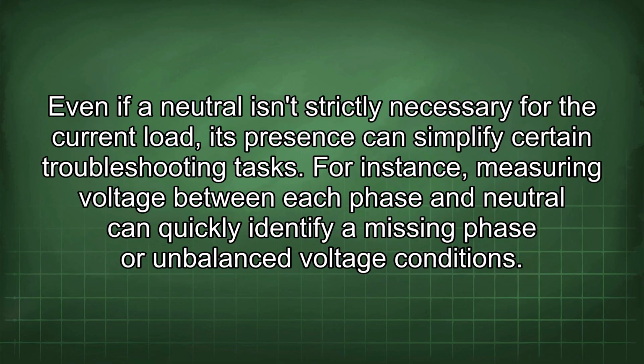Even if a neutral isn't strictly necessary for the current load, its presence can simplify certain troubleshooting tasks. For instance, measuring voltage between each phase and neutral can quickly identify a missing phase or unbalanced voltage conditions.